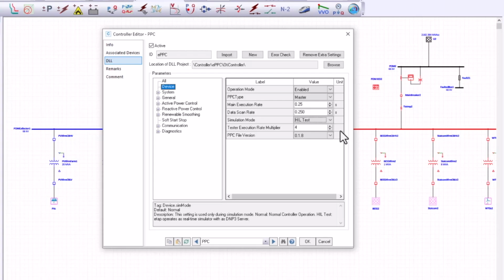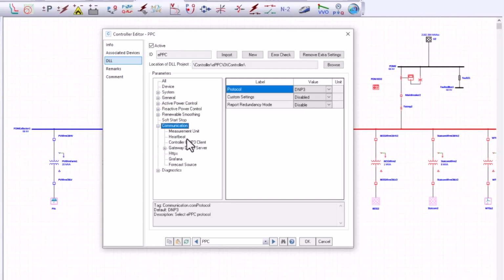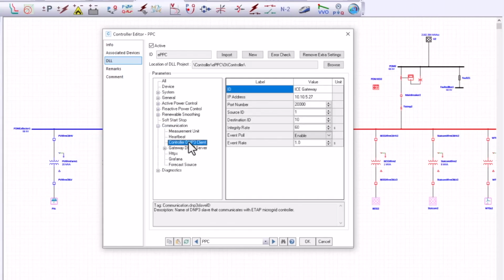Next, we need to configure DNP3 communication settings, specifying details such as the IP address and port number of the DNP3 server and other DNP3 communication protocol related settings. This allows ETAP to communicate with the external EPPC hardware and send and receive real-time data as if it were connected to the actual power plant.